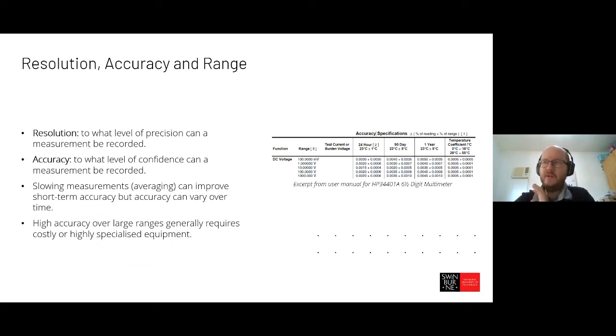Now, that doesn't mean you 100% need that for every experiment, right? Because often what's being offered in those instruments is the ability to measure very small changes on very large signals. So at 6 digits, if you've got a 1 volt signal or a 1 ohm device, you might be able to measure down to 1 microohm, right? But with the 8.5 digit, or with more digits, a larger instrument, you can get down into the nanoohms. Whether or not you need that, it's up for debate. Sometimes you might find that there's a different setup that can give you the same data. It might just take a little more work on the front end.